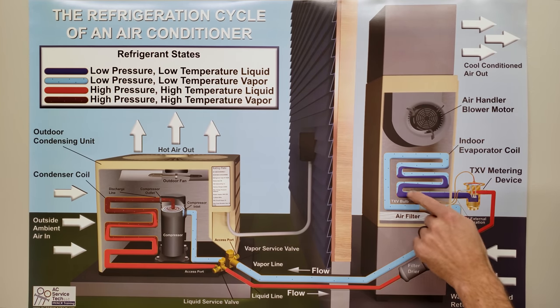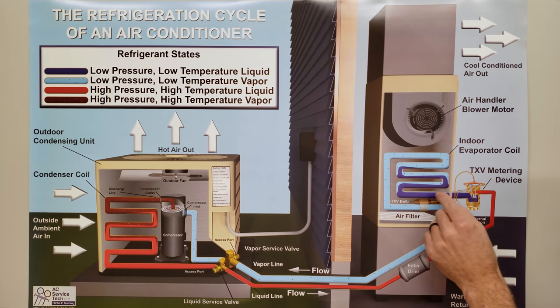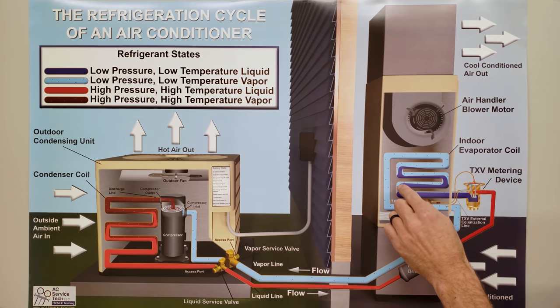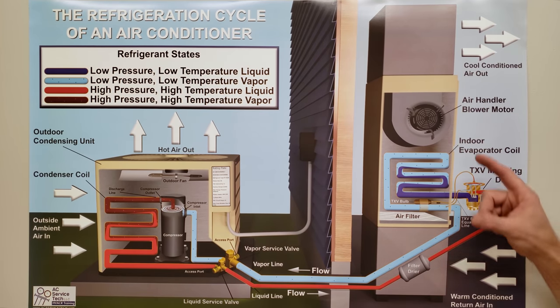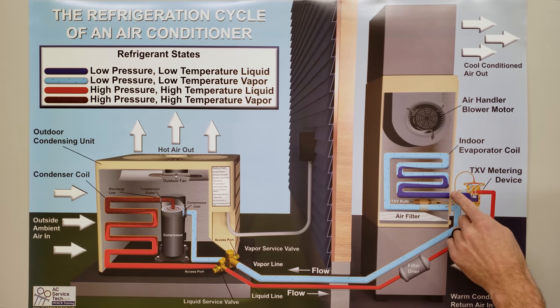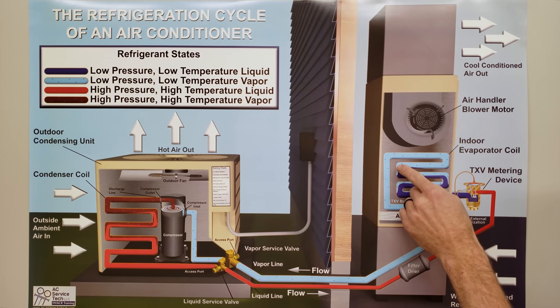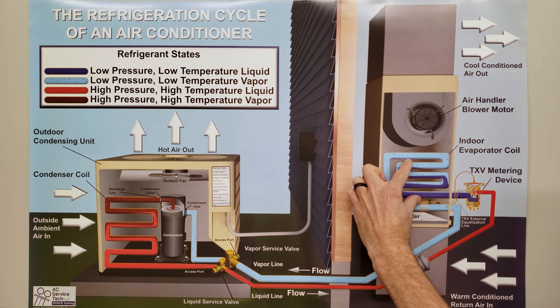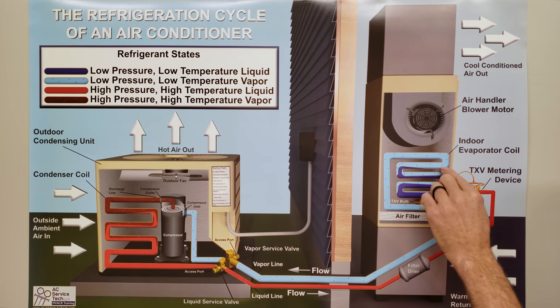As long as the refrigerant is saturated, it will absorb more and more heat without increasing in temperature. What changes is that the amount of vapor in the saturated mix keeps increasing while the amount of liquid decreases — but it stays at 40°F throughout. During this entire time it's been absorbing a large amount of heat energy from the air. Once it's completely in the vapor state, the temperature begins to increase.